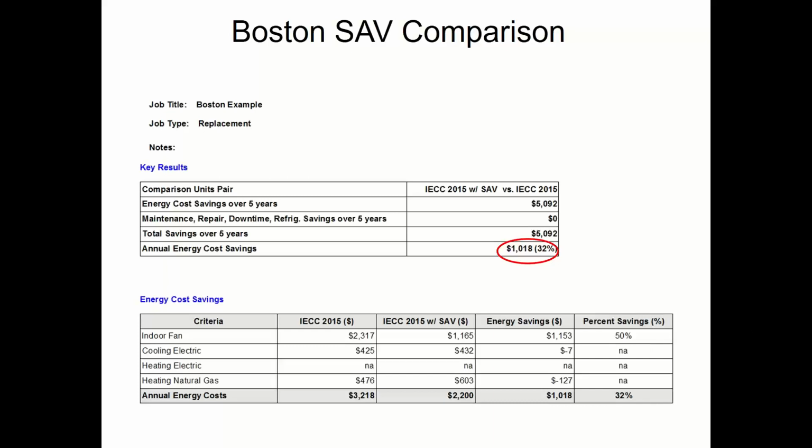In the case of these manufactured packaged small tonnage rooftop units, you're not going to get any choices whatsoever on what you want the VFD to be. The manufacturer is going to have a checkbox when the unit gets ordered. Do you want a VFD controlled staged air volume? Yes or no? That's it. You're not going to be able to pick any options on the VFD. It's not like we have on large chillers or on a custom air handler, where we can pick whatever VFD we want from any manufacturer with any features we want. It's not going to be like that.